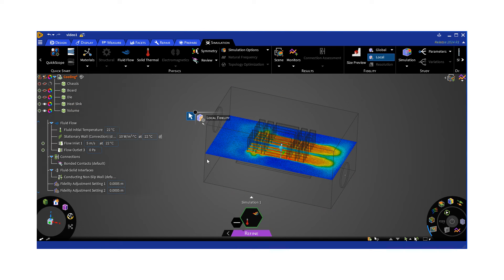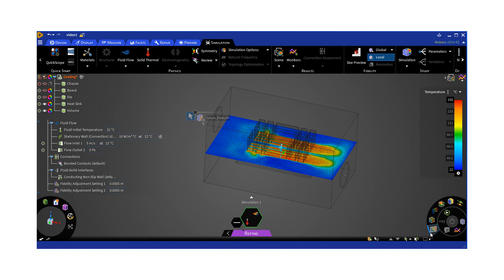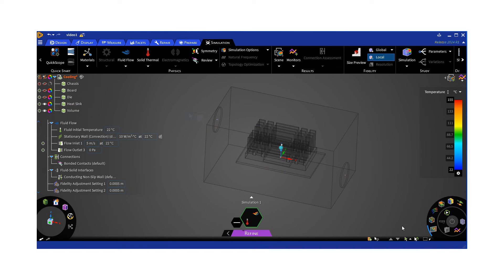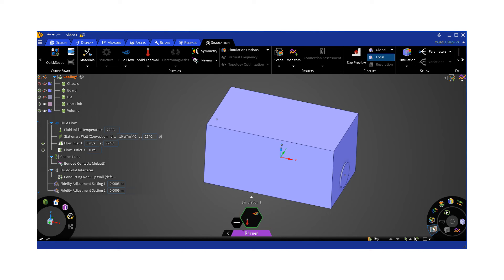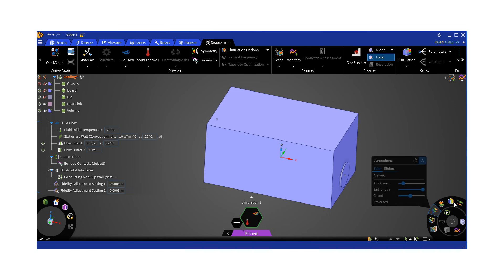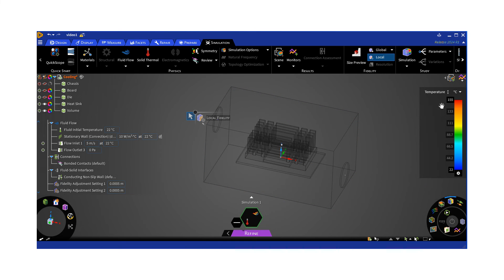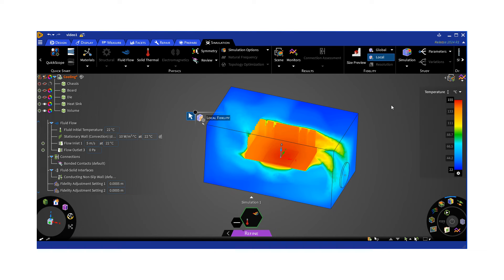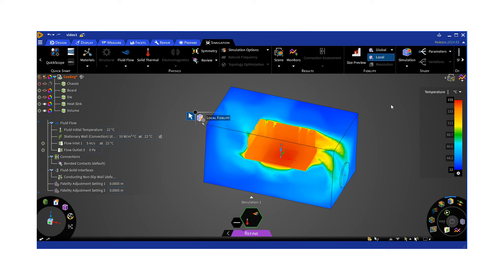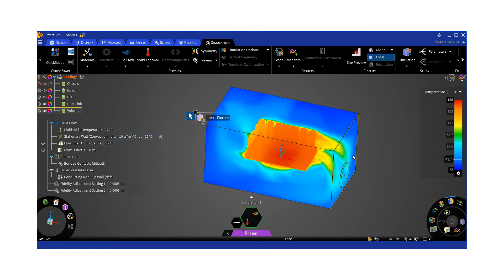Once the solution is complete, we'll get a figure like this. Let's turn off the direction field and turn back the contours on. What we do see is the peak temperature of 155, which is slightly under the 170 degrees C we had under the explore option. The two results seem similar, the flow fields also look pretty similar. Temperature contours look similar. So that's a good indication that we also had a valid result in the explorer mode. In fact, this run was pretty fast. It took under 10 minutes. We can go ahead and make it finer and finer. It's up to us.